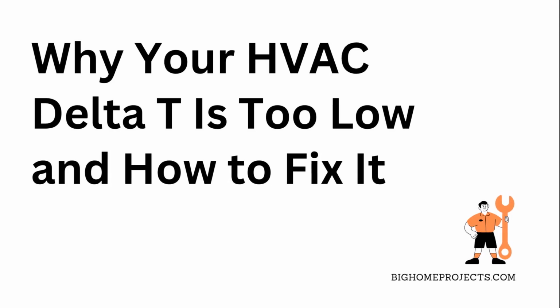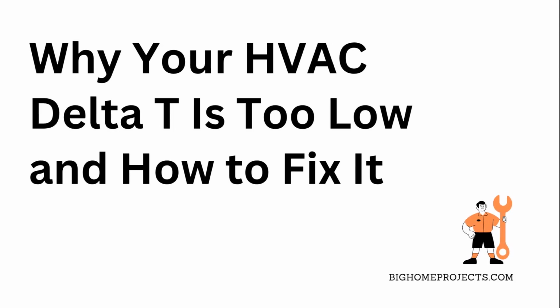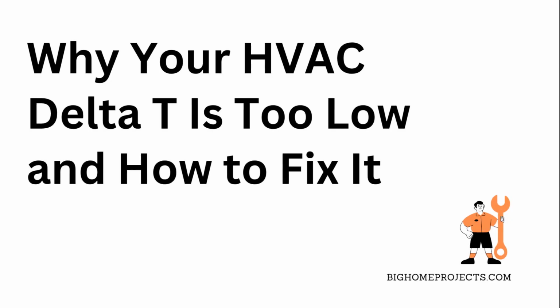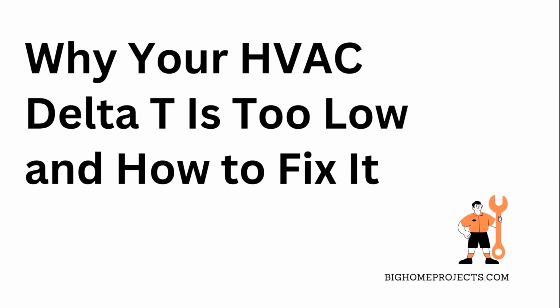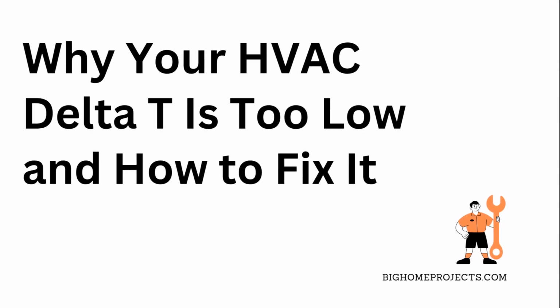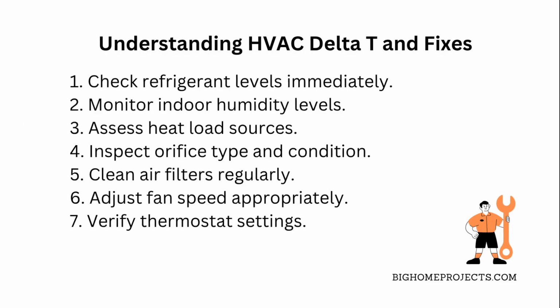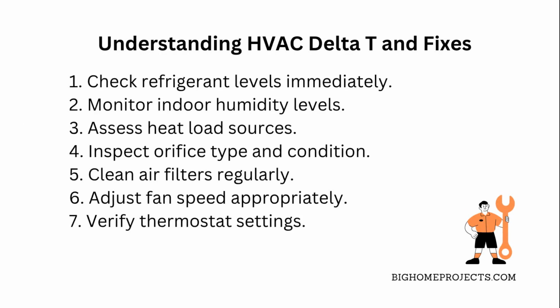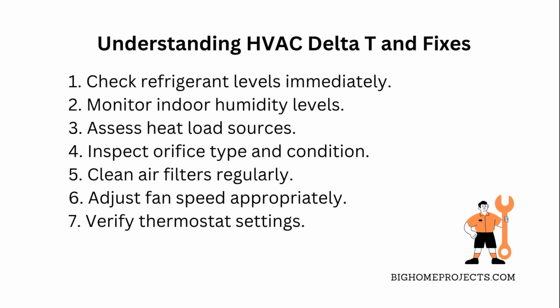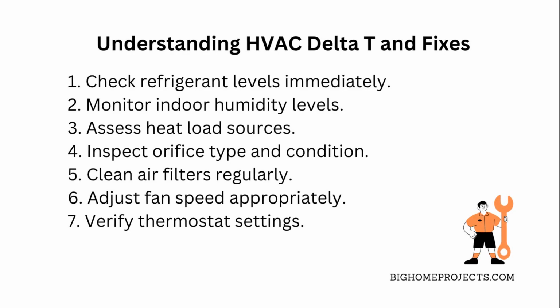If your HVAC Delta T is lower than 18 degrees Fahrenheit, you gotta pay attention, because that low Delta T can seriously mess with your system's efficiency and comfort. Okay, so first off, if you see that Delta T number dropping below 18 degrees, start by checking if your refrigerant level is low, because that's a classic cause.